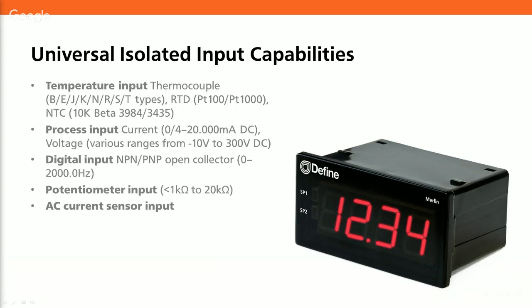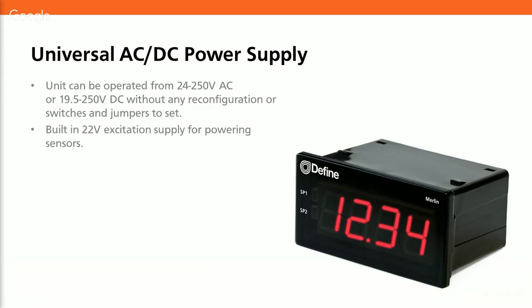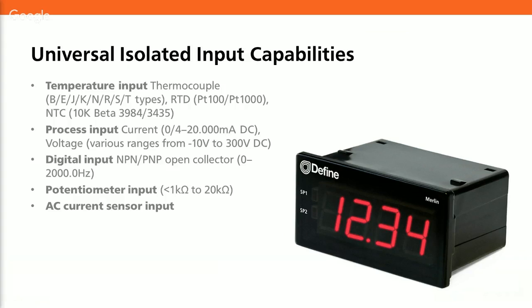The voltage input can also be configured in many different ranges, from as small as plus or minus 200 millivolts all the way up to 300 volts DC. On top of these, the Merlin also has a digital pulse input that can be used with pulse signals from devices such as flow sensors, and has a working range from 0 to 2 kilohertz. It also has a potentiometer range for use with ratiometric sensors, and for measuring high current signals, it can be paired with one of our optional external AC current sensors.